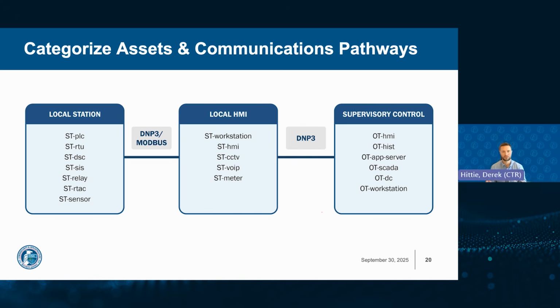Now, what connects these zones are the conduits. So for example, the conduit from zone 1 to zone 2 may use serial or Ethernet connections to pass process data and alarms. Here you see Modbus and DNP3 between the local station and the local HMI zone, representing the field protocol communications. The conduit from zone 2 to zone 3 is often an IP-based link, carrying telemetry to the SCADA server and commands back to the station.